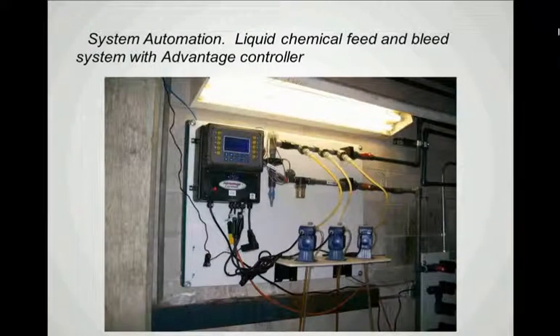One of the helpful tools for controlling not only the cycles of concentration, but also the chemical dosages in the cooling tower and the cooling tower bleed is to automate the system. And here we see an example of a liquid chemical feed and bleed system utilizing an Advantage controller. There are many different controllers on the market. This happens to be the one that was installed at this location.